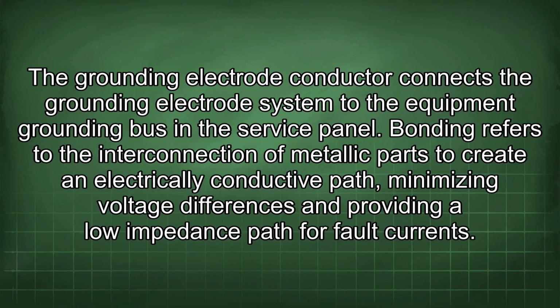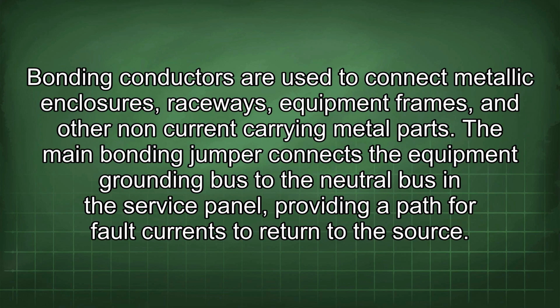Bonding refers to the interconnection of metallic parts to create an electrically conductive path, minimizing voltage differences and providing a low impedance path for fault currents. Bonding conductors are used to connect metallic enclosures, raceways, equipment frames, and other non-current carrying metal parts. The main bonding jumper connects the equipment grounding bus to the neutral bus in the service panel, providing a path for fault currents to return to the source.